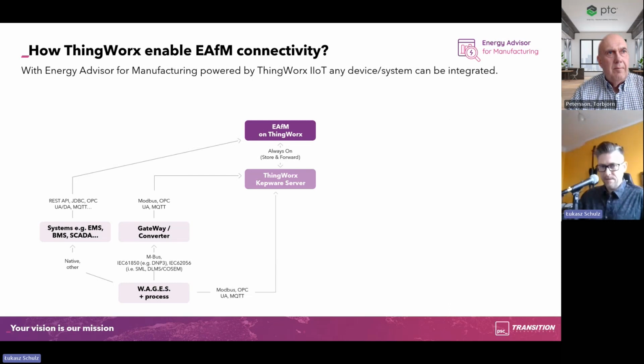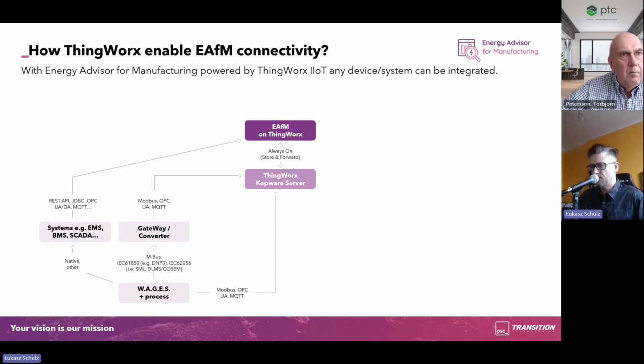It also happens that a lot of meters communicate only with their dedicated protocols, like MBus, which is metering bus, or DLMS COSEM. COSEM stands for Companion Specification for Energy Metering, and they cannot be directly connected to ThingWorx. Then we advise customers to go with gateways or converters to switch to more open protocols.